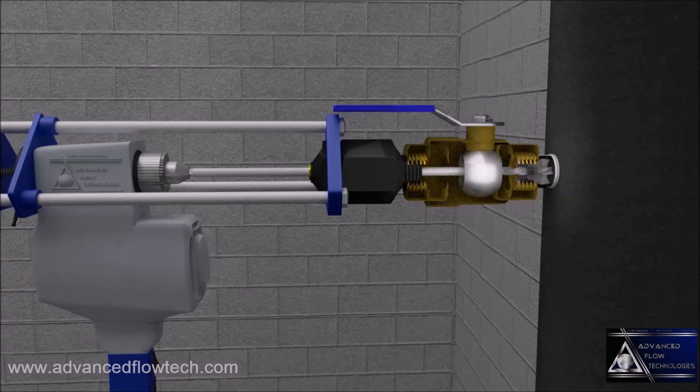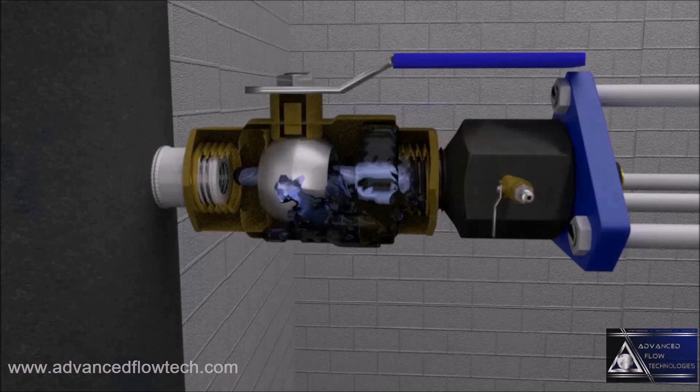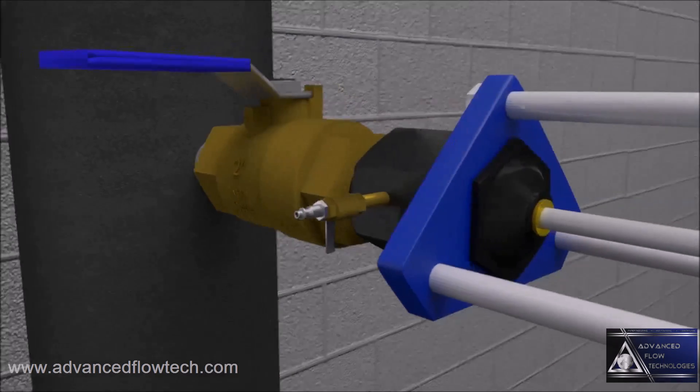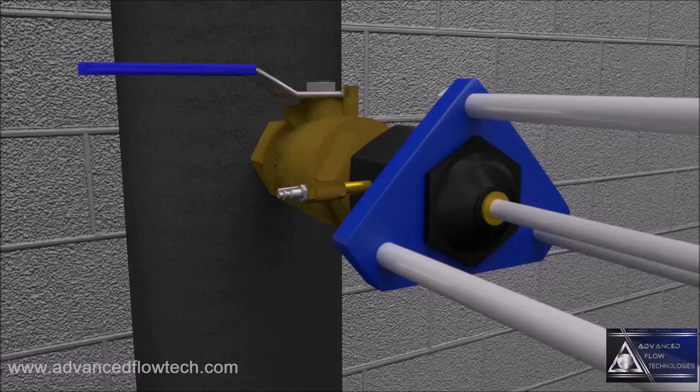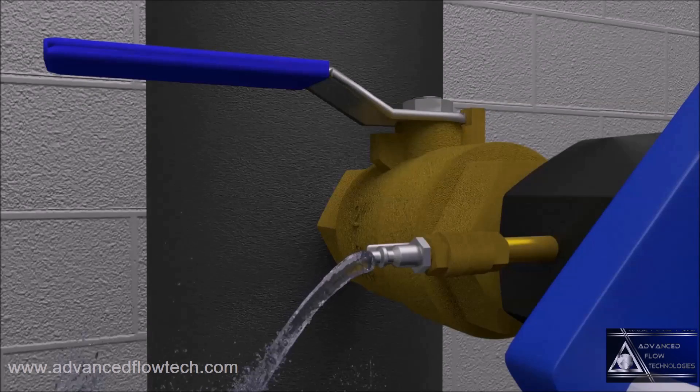During the hot tap procedure, the water pressure will be contained within the insertion valve and hot tap machine. The isolation valve will then be closed and any pressure will be released prior to removing the hot tap machine.